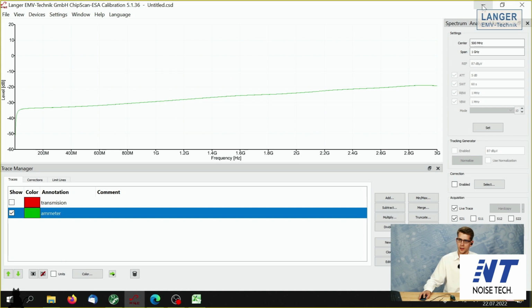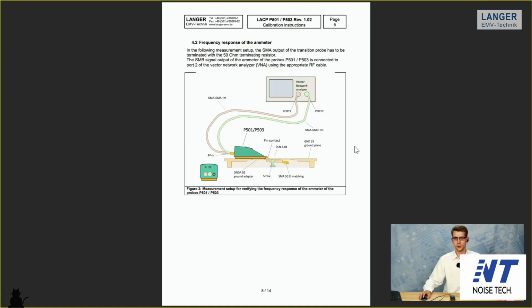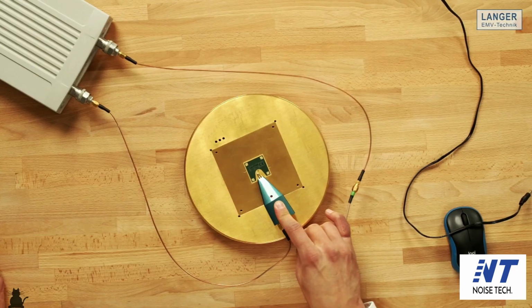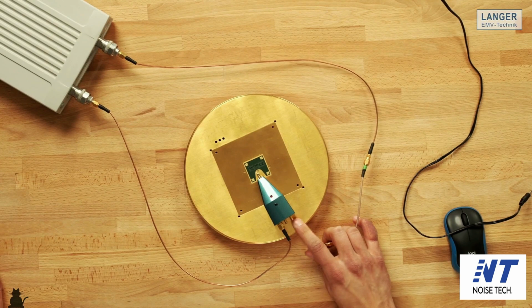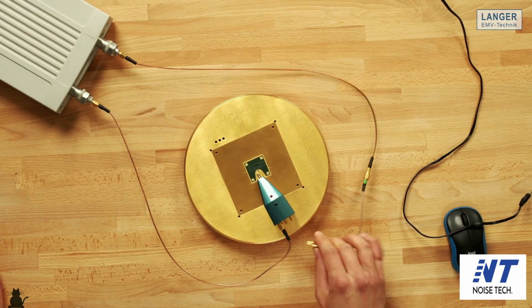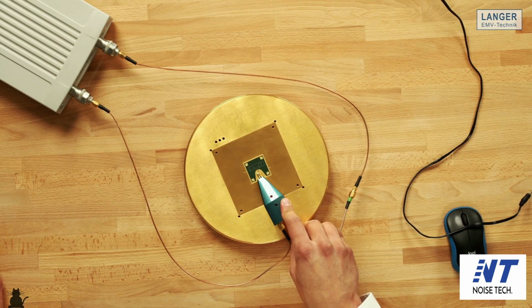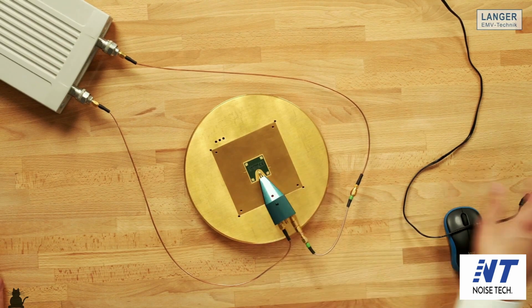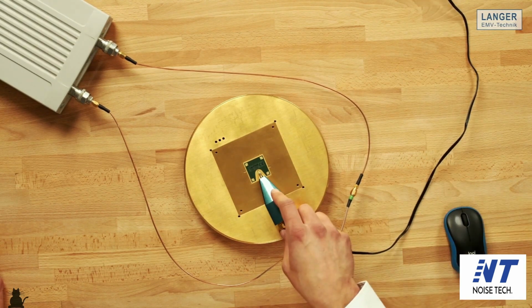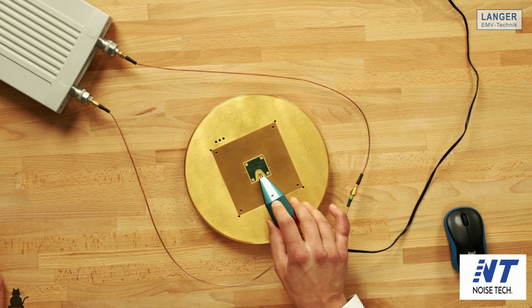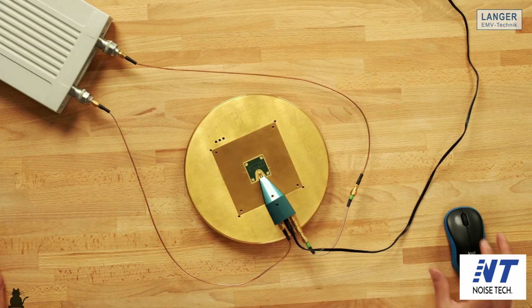So the last thing we need to do now for the calibration is the calibration of the voltmeter. In comparison to the calibration of the ampere meter, we just need to change the SMB connector from the ampere meter output to the voltmeter output, like this. Again, connect the supply of the probe and check if we are connected to the pin. And the LED is on, so I'm connected.